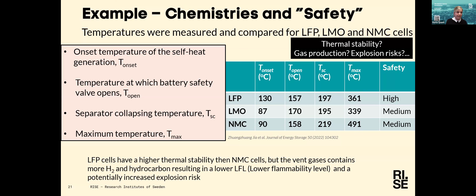There are many strategies to avoid incidents, also divided into different levels. At cell level, it's mostly the material affecting safety, and there's a lot of research into batteries with, for example, solid or semi-solid electrolytes. Design is also important—where can gases vent? At module and pack level, we have the BMS, TMS system, and thermal barriers to prevent thermal runaway from propagating if it has started in one cell, plus safety valves, CIDs, and fuses, and so on.